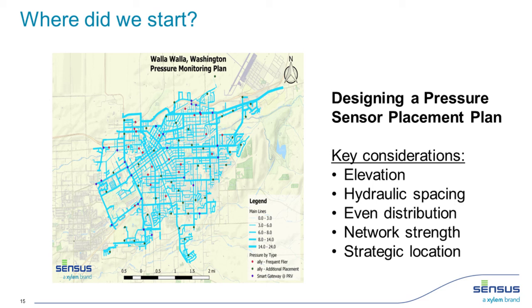If there is an alarm, you're going to hear about it between 0 and whatever your MSR setting is, be it 5 minutes, 15 minutes, or an hour. But that goes back to what Adrian was saying about setting the alarms and thresholds in the system. If you're just looking at the server side data, you're not going to see that. But if you're actively managing it the way Walla is, and they understood their system and set the threshold to say, hey, if it's below this we want to know about it, then that's when you would see those alarms.